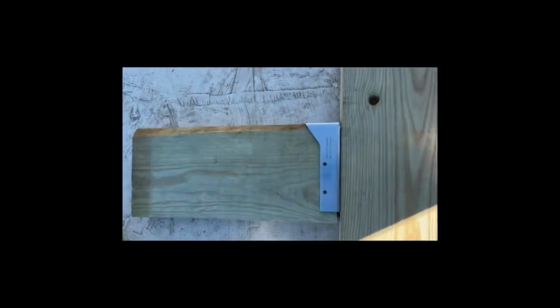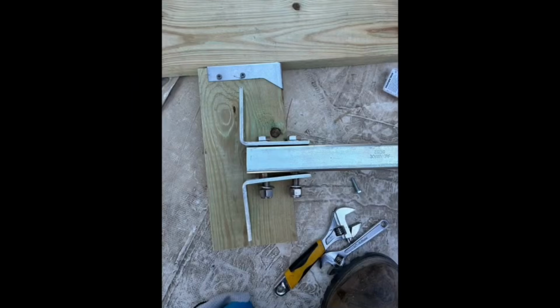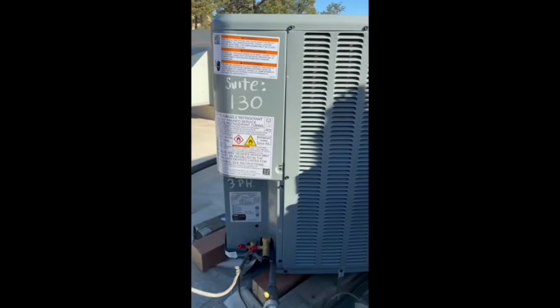And sitting on top of some pressure treated 4x4s. I also need to make a stand for the disconnect switch, because on the new unit there's no good place to mount the disconnect switch on the side of the unit. We'd be blocking the panels or blocking the hail guards and the condenser coil. We don't want to do that. So just using some unistrut, some corner brackets, some pressure treated lumber, joist hangers.